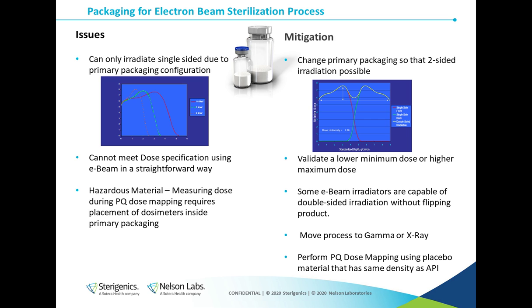One other consideration for processing in E-beam and other modalities as well is whether or not your product has a hazardous component, as it is necessary in E-beam for sure to include the product during PQ dose mapping of the process. So it might be necessary to use placebo product that has the same density, in this case, as the API, in order to do the dose mapping validation of the process.